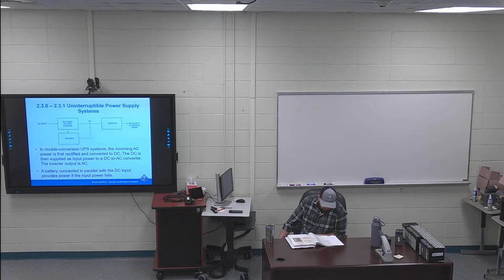Right before the bullet points on page 16, or the first set of bullet points, I've got that sentence highlighted. The double conversion system has several advantages. I've got all the bullet points highlighted. Excellent frequency stability, high degree of isolation from various incoming line voltages and frequency. Zero transfer time possible, which is where you won't see the blip or anything like that. Quiet operation, can provide a sinusoidal output waveform with low distortion. So that just means that it can provide clean AC power.